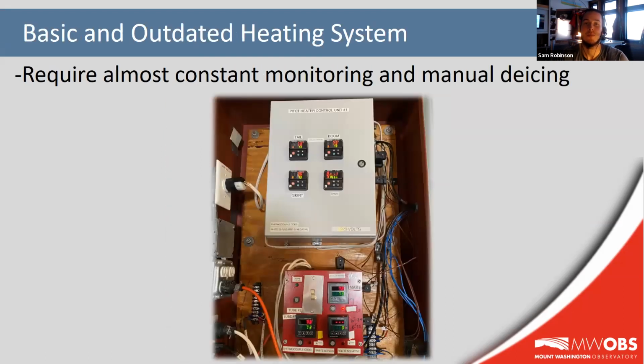So the last big area of improvement is the heating system on pitot 19, which is basic and beginning to be outdated. The heaters were upgraded to higher wattage elements in 2019 when the name change occurred, but there was still plenty of room for improvement. In the worst of icing conditions, which are a pretty common occurrence during the middle of the winter, the heaters simply cannot keep up even when cranked up. I know from personal experience that sometimes it's required to go up to the top of the tower multiple times in an hour just to make sure that the instrument is clear of ice buildup.